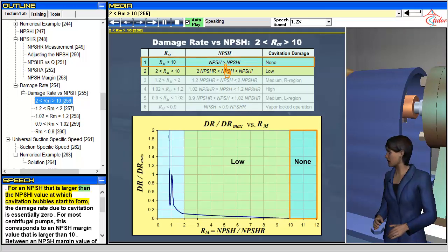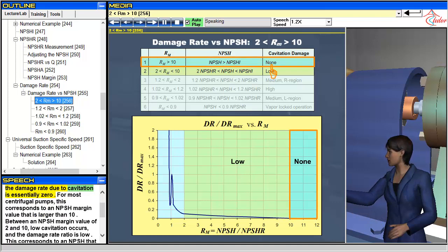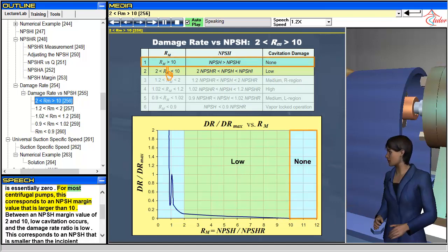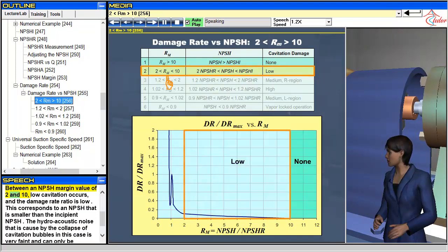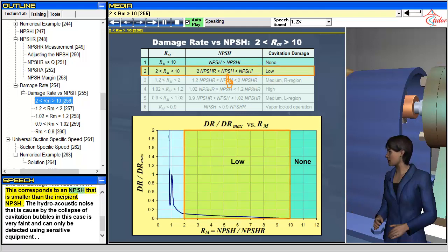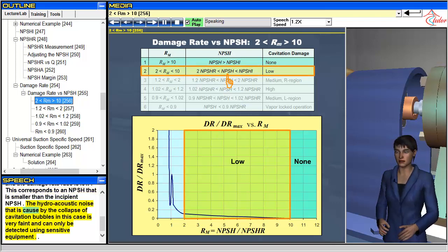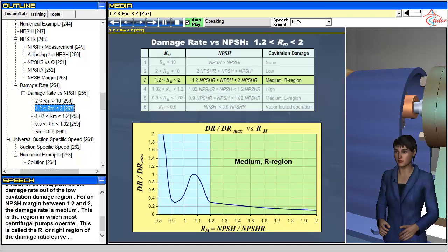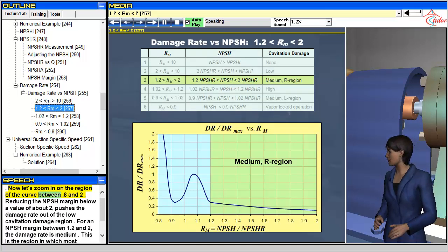For an NPSH larger than the NPSHI value at which cavitation bubbles start to form, the damage rate due to cavitation is essentially zero. For most centrifugal pumps, this corresponds to an NPSH margin value larger than 10. Between an NPSH margin value of 2 and 10, low cavitation occurs and the damage rate ratio is low. The hydroacoustic noise caused by the collapse of cavitation bubbles in this case is very faint and can only be detected using sensitive equipment.